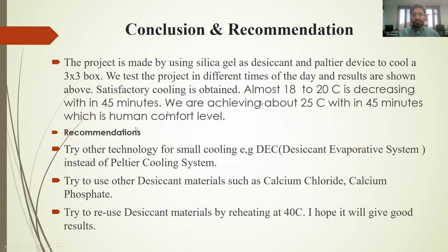Satisfactory cooling is obtained. Almost 18 to 20 degrees centigrade is decreased within 45 minutes. We are achieving about 25 degrees centigrade within 45 minutes, and we can say that it is a human comfort level. And these are some recommendations for future work.